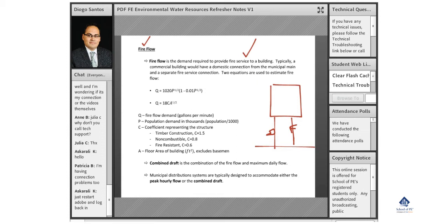There are two ways to calculate what the fire flow is. This equation is more a macro equation: fire flow in gallons per minute is a factor of the entire population in thousands. As your city grows, so does your fire flow demand.